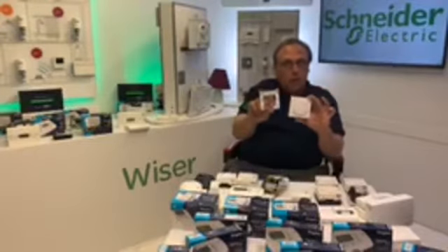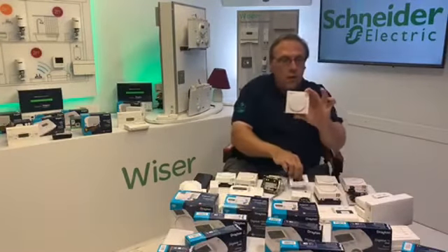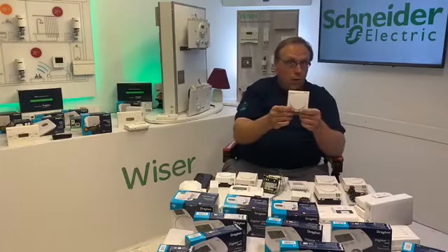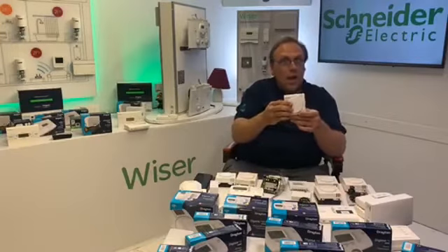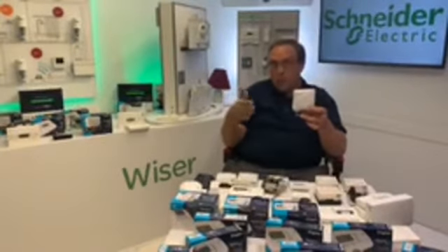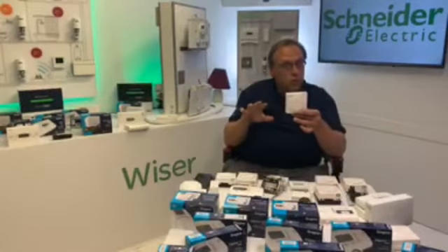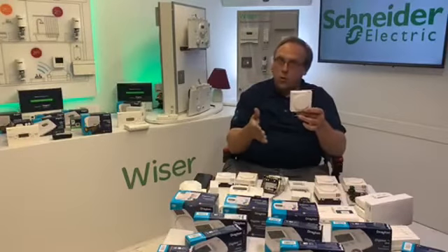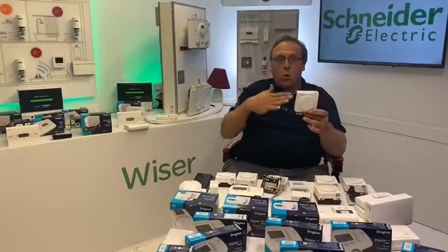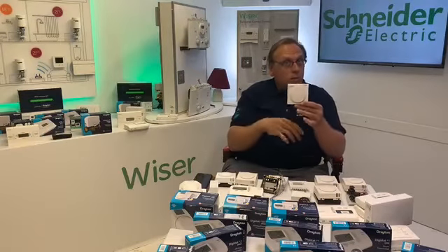RTS4, same backplate, although you've got a fully populated rail of terminals here, because the RTS4 is volt free. So the wiring on this is exactly the same really as a single channel timer, where you've got a permanent supply in, so your 230 volts comes in on a permanent supply onto the first two terminals, and then you've got control of what switches. So if you want to switch 12 volts or 24 volts, or if you want to get to the normally closed contact, you can do that with an RTS4.